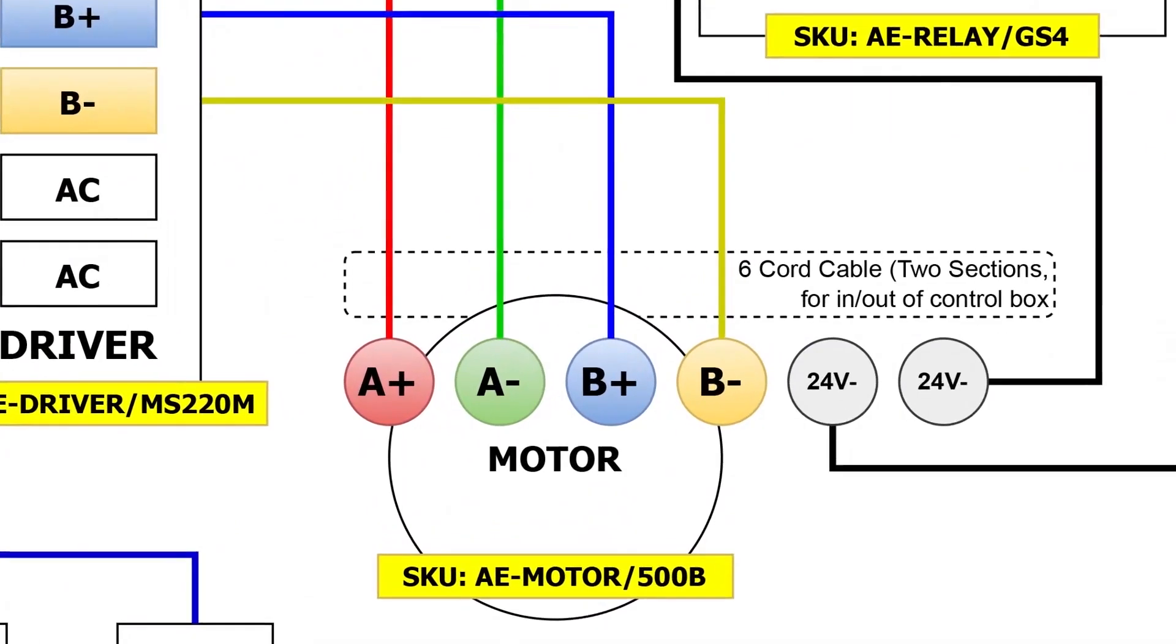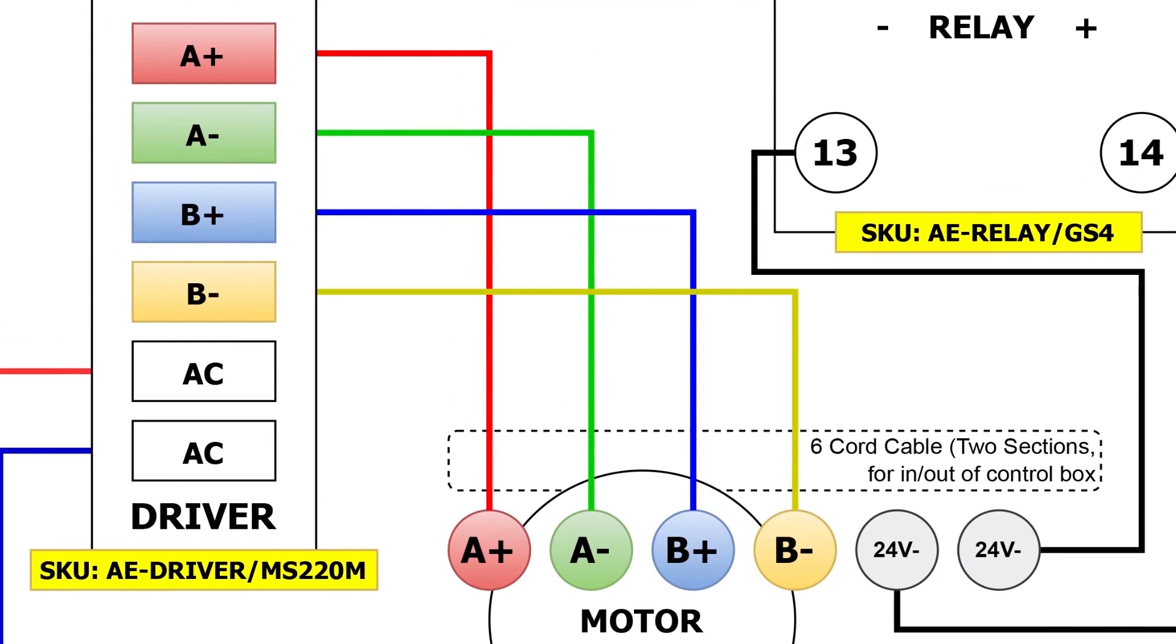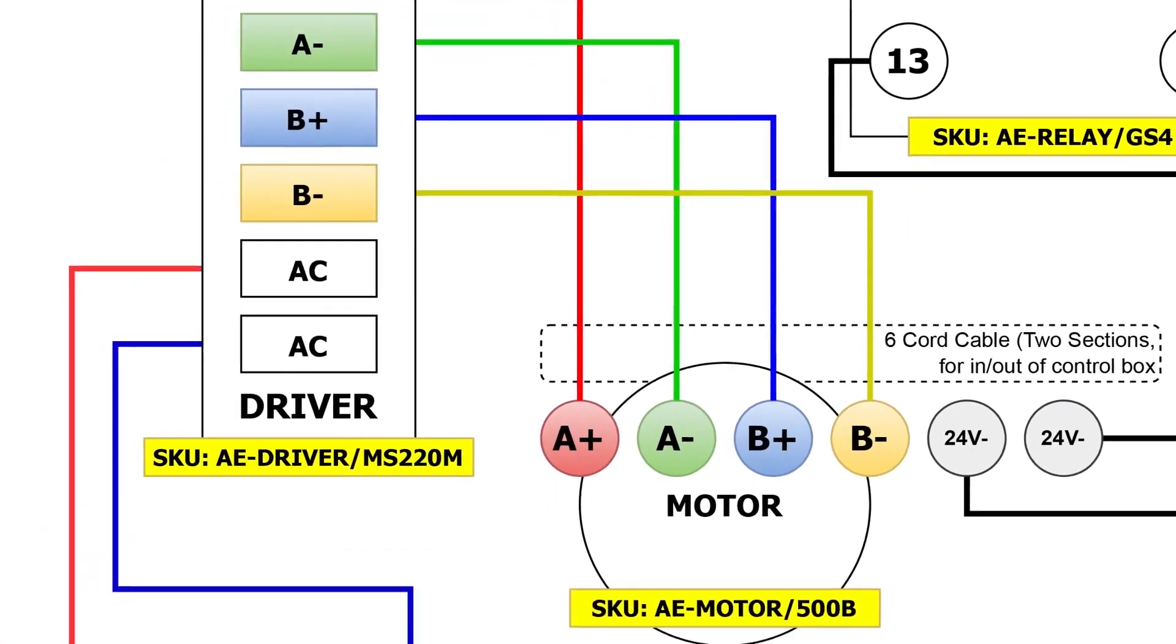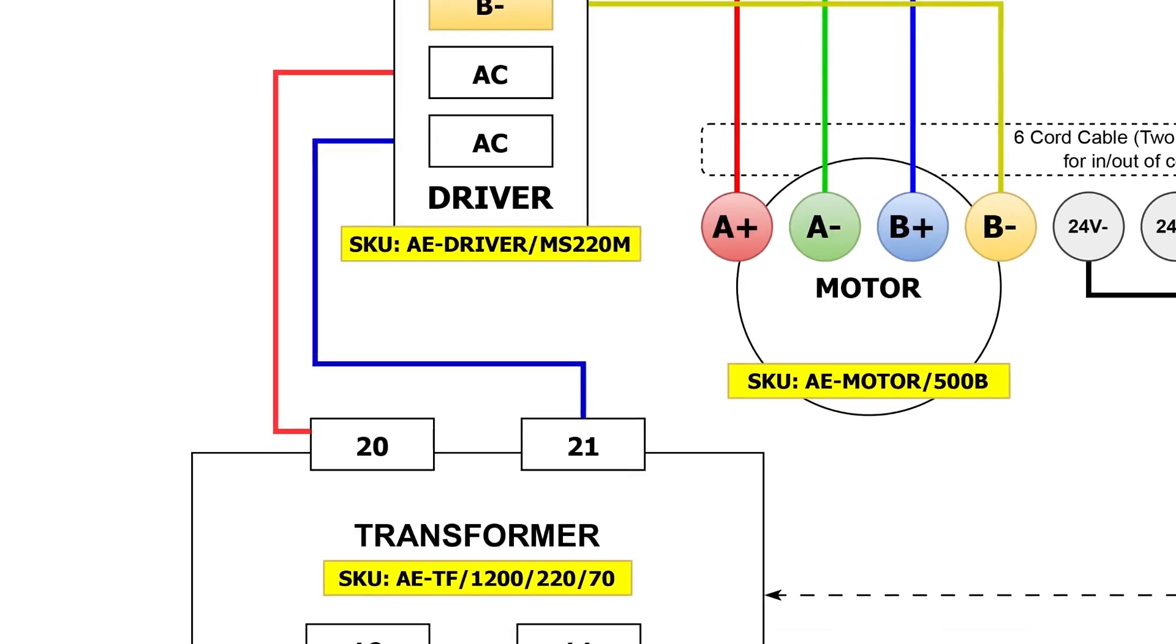Join A positive, A negative, B positive, and B negative on the motor terminals to A positive, A negative, B positive, and B negative terminals on the driver. The driver AC terminals go to terminals 20 and 21 on the transformer. Terminals 10 and 11 on the transformer are for 220 volts AC.